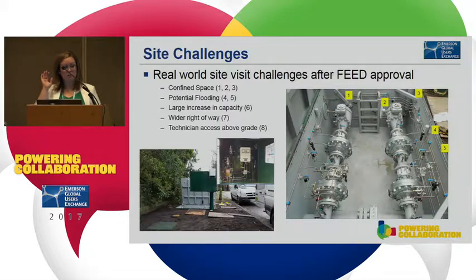So this station could completely flood, and the overpressure protection will stay completely intact. Another thing we did — a lot of the old set designs were just boxes with lids coming down on top. Here you can see there's a much wider lip on this box. The fabrication group recontoured the whole edge of the lip to create channels that keep the water out as much as possible.